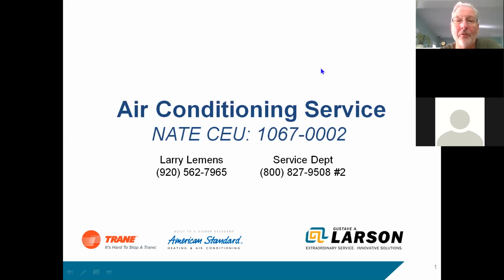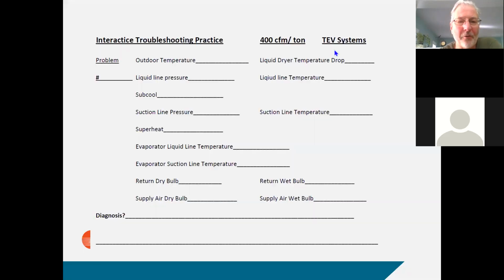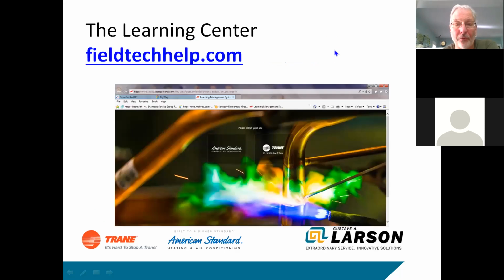So if you've got any questions, unmute yourself and just jump in. Give me some direction here, and I'll go where you guys want to go. One thing I want to put out, this is a training sheet that I use. We talked about getting information. If anybody wants to shoot me an email, I'll send these forms to you. Basically, when you're looking at the refrigeration side, we've got the compressor running, everything's working. Then we want to look at the numbers: the temperatures, the pressures, check out the subcool, check out the superheat, wet bulb readings. We've got to know what this information is in order to do a good job of troubleshooting these systems.